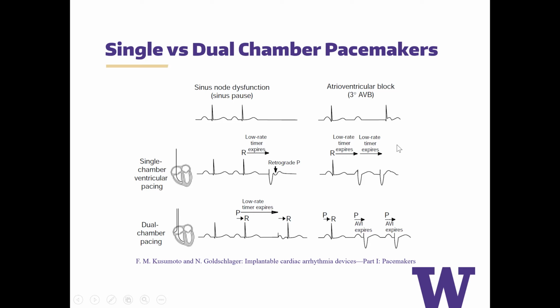So in these patients, if all they got was a single chamber ventricular pacemaker, what happens is that at the very last sensed R beat, you have a low rate timer that starts. And when that expires, you get a paced beat from the ventricle. And then from that very last paced beat, you have another low rate timer that starts. Within this interval, if there is another sensed QRS that's intrinsic, it would inhibit the pacemaker's paced beat. But because there isn't, the next paced beat comes, and the interval between these two is determined by the low rate, whatever low rate you set the pacemaker to be.